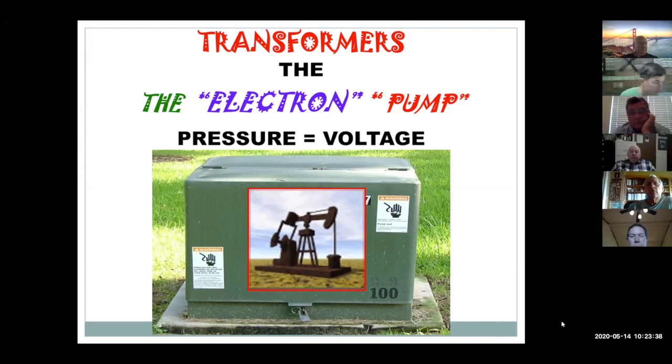And if you look real close above 100, it's 19.9. So this is an underground distribution at 19,920 volts, sitting out on this pad in this fellow's yard, and 100 yards away is his brand new swimming pool. So we had to do some special grounding out there just to be sure. You're not supposed to have any voltage stray coming around, but you want to be sure.